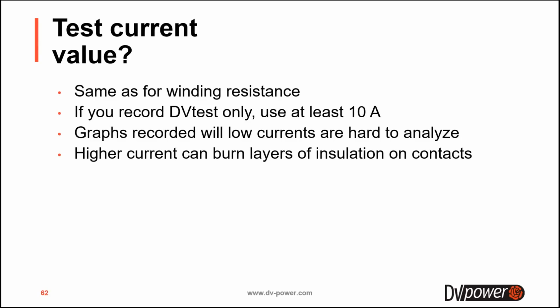Another question is test current value. So what test current should you use for doing the DV test? If you do it together with winding resistance, of course you do it with the same current that you use for winding resistance. If you are recording only the DV test without winding resistance, you should use at least 10 amps. This is because graphs recorded with lower currents can be very hard to analyze. You can have a lot of noise on the graph. You may not be able to clearly see all the characteristic points on the graphs.